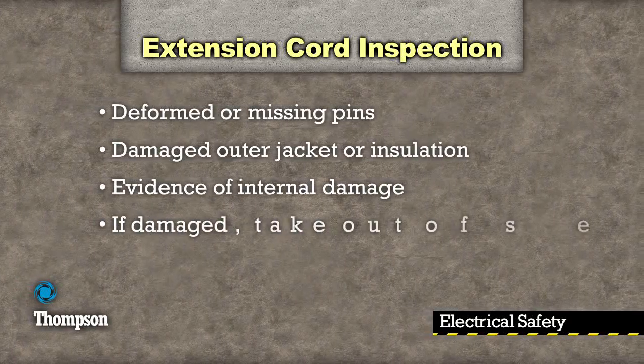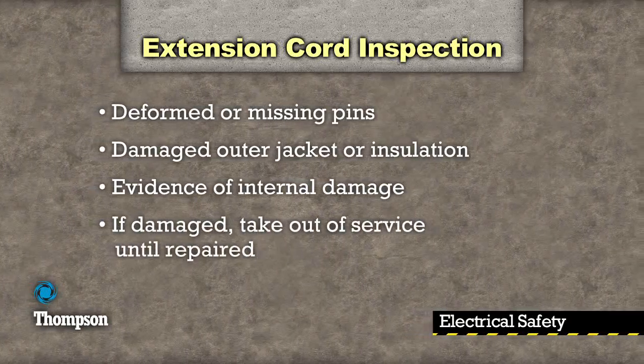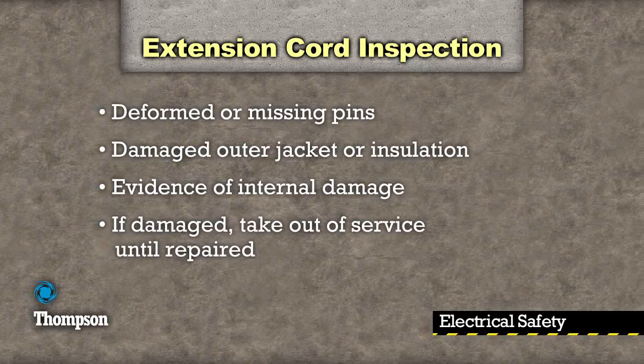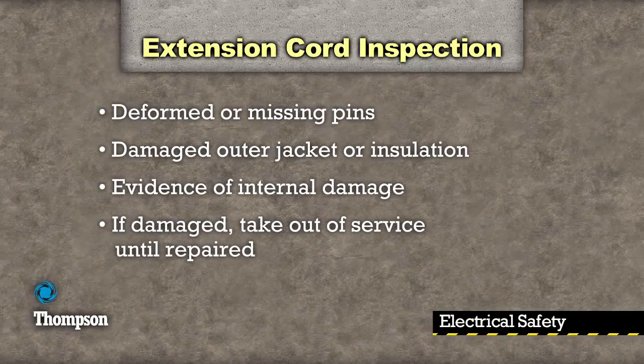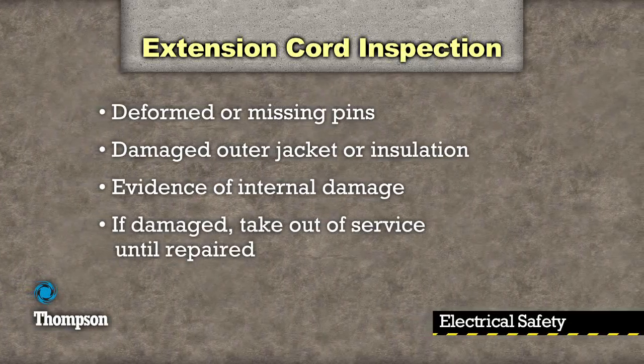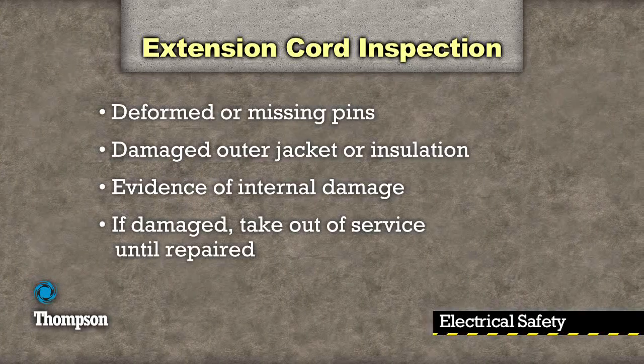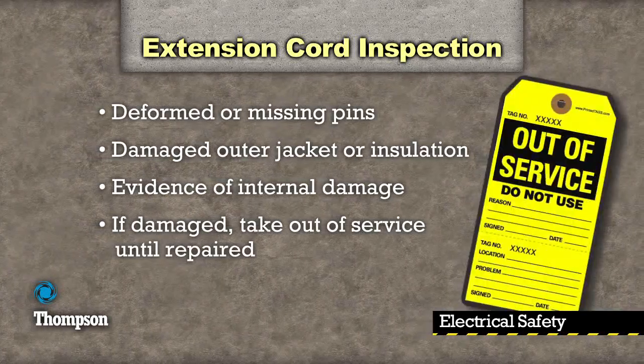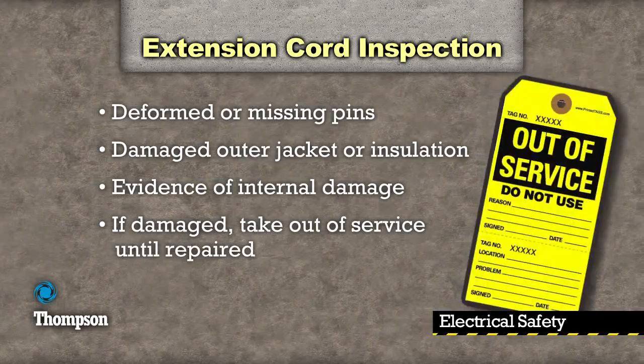Examine the plugs for deformed or missing pins. Inspect the outer jacket insulation of the cord for cuts, abrasions, or signs of wear. Is there evidence of internal damage, such as a pinched or crushed outer jacket? Again, if a cord is damaged, tag it out of service and repair or discard it.